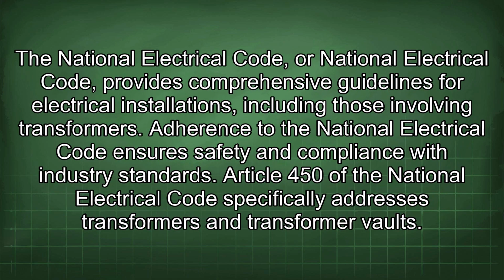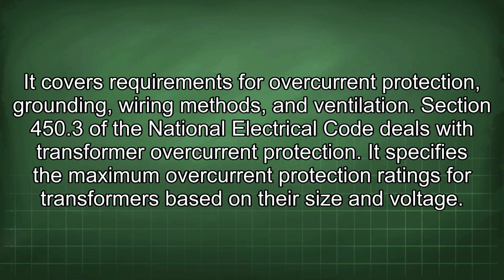The National Electrical Code provides comprehensive guidelines for electrical installations, including those involving transformers. Adherence to the National Electrical Code ensures safety and compliance with industry standards. Article 450 of the National Electrical Code specifically addresses transformers and transformer vaults. It covers requirements for overcurrent protection, grounding, wiring methods, and ventilation.